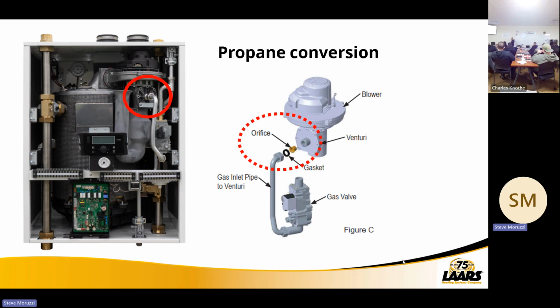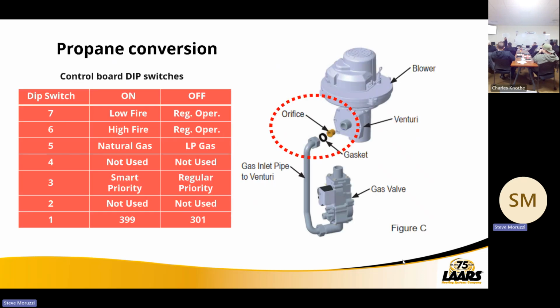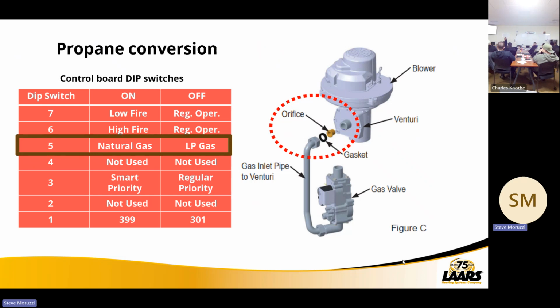And then you have your orifice change out, and that's it. What's left is your dip switch. So again, less than 4 minutes. And then you would adjust dip switch 5 from natural to LP.